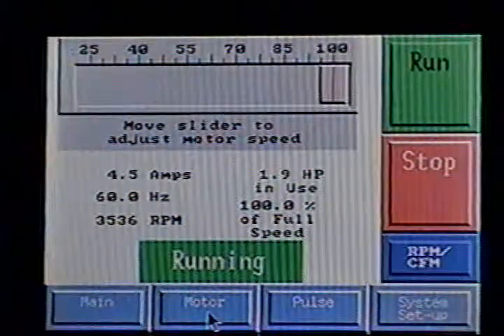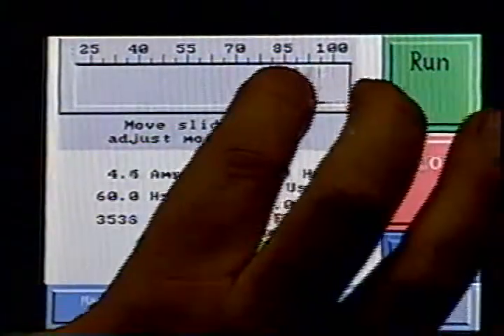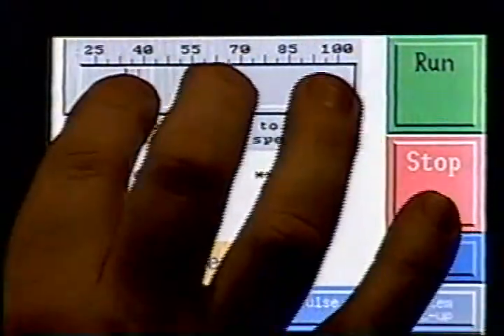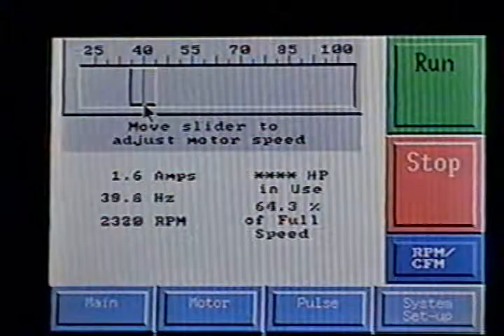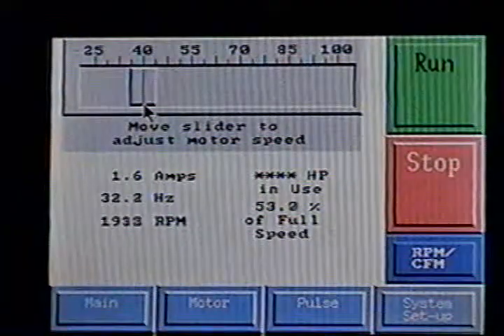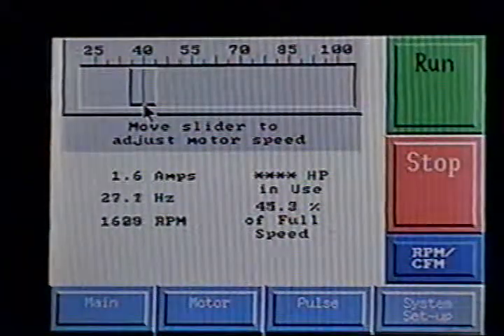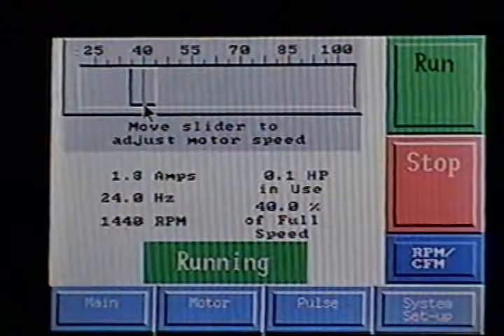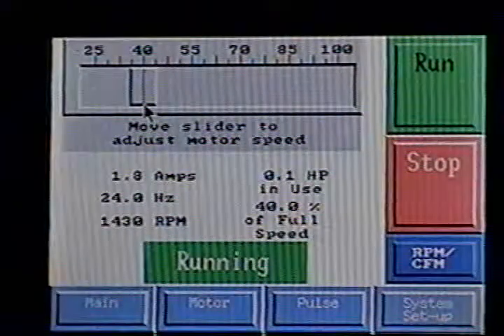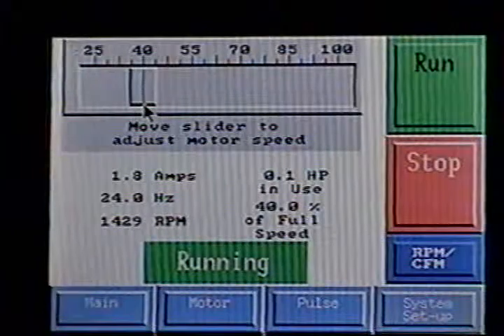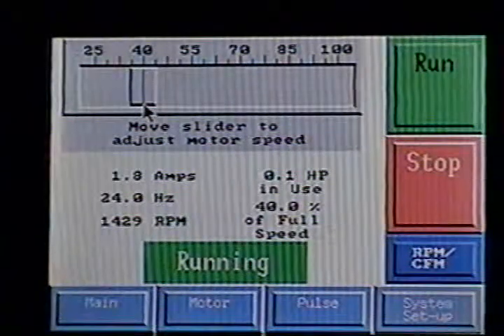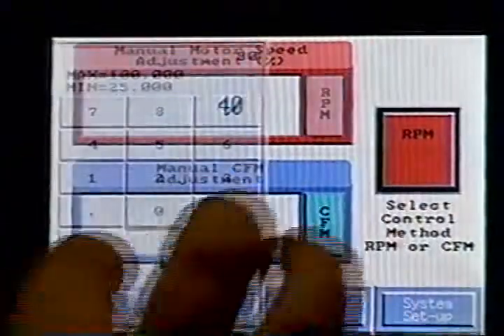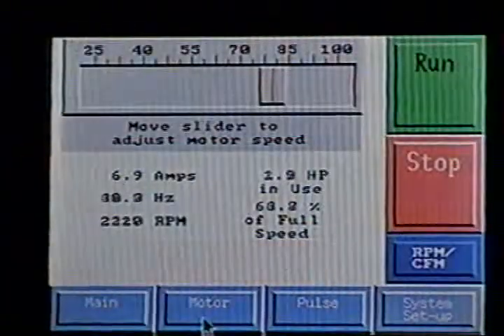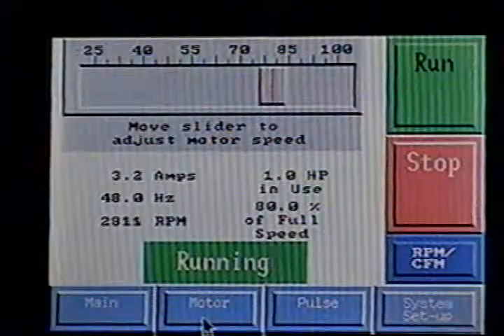So it'll be a little easier to talk over, I'm going to slow the motor down to roughly 40%. A little easier to hear. It's that simple to control the motor speed. If you want to directly control the motor, there it is. If you want to go in and do your cost justification based on 80% of the motor speed, we'll just set it at 80%. And you'll have 80%, that's where it's going to run.